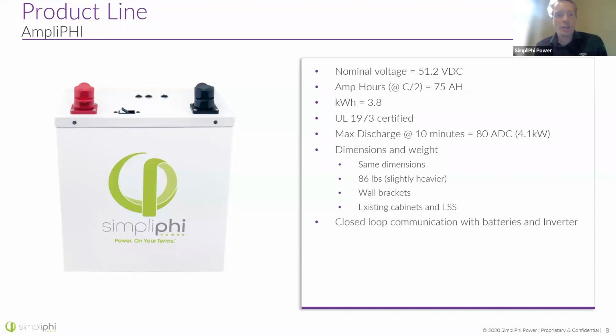The nominal voltage on these batteries is 51.2 volts DC. What nominal voltage means is when the battery's at a 50% state of charge, that's the resting voltage you would see. If the battery is not running loads and it's at a 50% state of charge, the voltage you would see would be 51.2 volts.